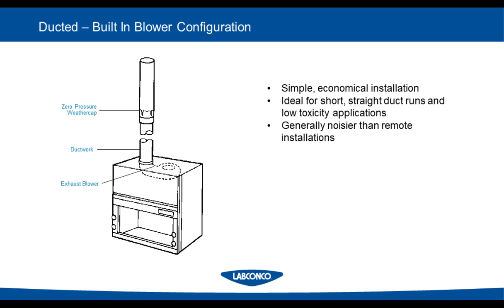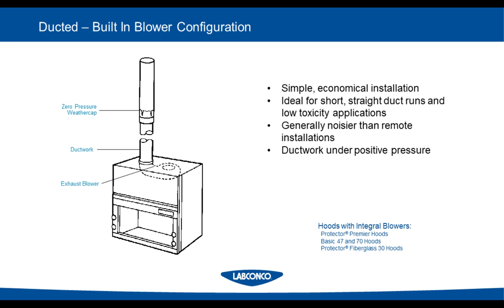The major downfall of a built-in blower configuration is that the ductwork is under positive pressure. So in contrast to the remote blower situation, if there's a leak or a seam or a crack in the ductwork, the hazardous material that is being dealt with in the fume hood is actually going to be pushed out of those seams and into the lab space. So that's why all of this is for very simple situations and setups, because it's not the safest situation. And straight duct runs are a great way to eliminate that type of risk.